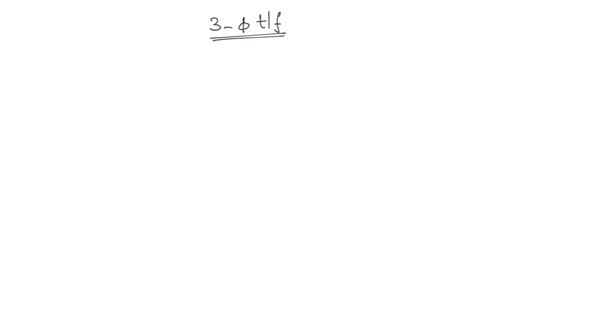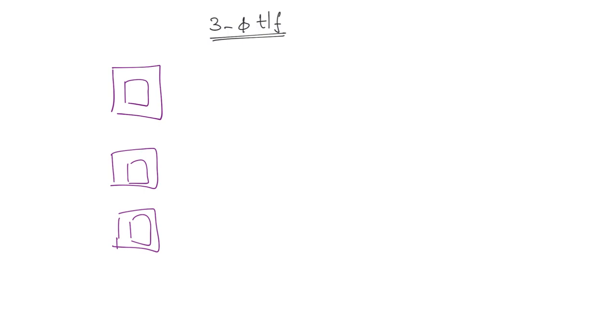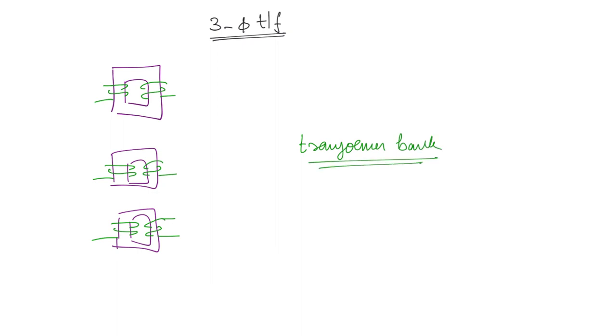These three-phase transformers can either be formed by using three different single-phase transformers. In a three-phase system, all three phases should be out of phase with respect to each other by 120 degrees, and the magnitudes should be the same. If the three single-phase transformers follow these conditions, you get a three-phase transformer, but this is called a transformer bank. If you are just using three single-phase transformers, it is called a three-phase transformer bank.